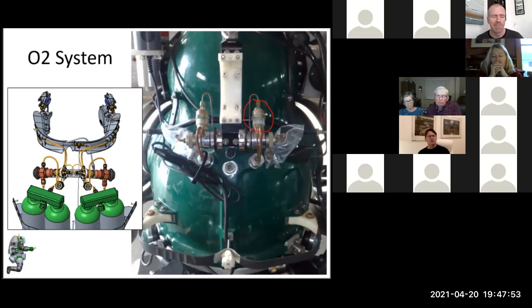You don't want 3,000 PSI oxygen accidentally going into your cabin. So on this side is high pressure oxygen, with a piston with seals on it, and this side is high pressure oil. If there's a leak in the oil line, the piston goes to the end of its travel and stops moving, and your cabin pressure gauge that reads the high pressure oxygen number will go to zero, and the dive will be aborted based on that loss of oxygen. That's important so you don't fill the suit up with oxygen.